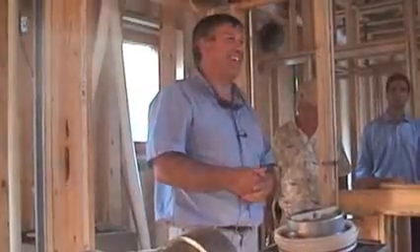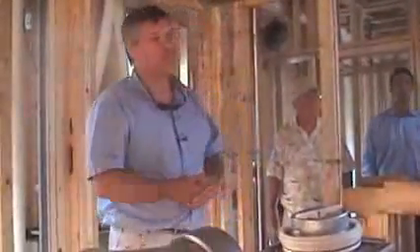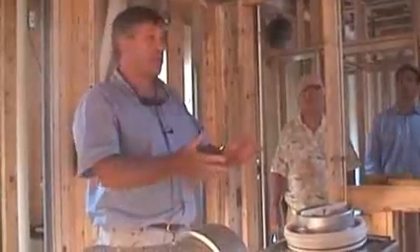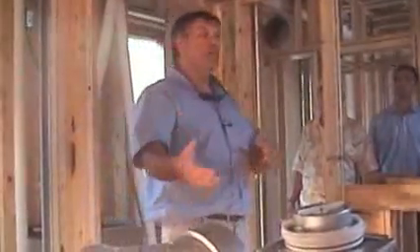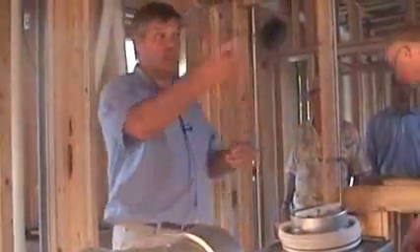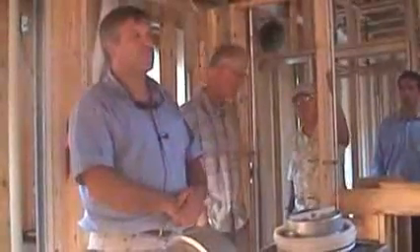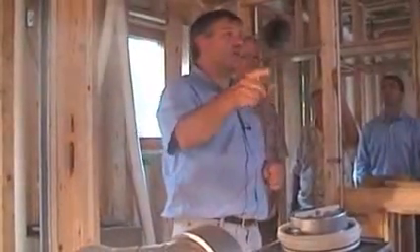You wouldn't want to change one? You could take the core off. Yes, ours are interchangeable. In some cases in New York City, for example, where they have very hot, humid summers, they like the ERV, but they have moisture issues in the winter. They want an HRV so that they get rid of that inside moisture. They switch them out. So that's possible. It takes 5 minutes. Very easy. And there's a small change in the programming. You have to tell the unit if it's an HRV or an ERV. That's it.